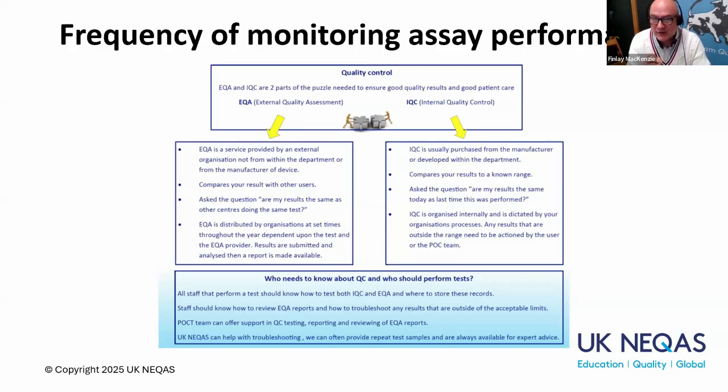Diane mentioned the frequency for some of the coag things. We have schemes, for example, where in laboratory land it tends to be monthly, 3 specimens. But in point of care land, we think it might be a little bit less frequent than that. Some of our point of care guys do want it as frequently as that, and I think that's a bit overkill, perhaps. Some of them we might have 2 samples rather than 3. We in chemistry don't like the idea of doing a single sample, but for other disciplines that might be sufficient.